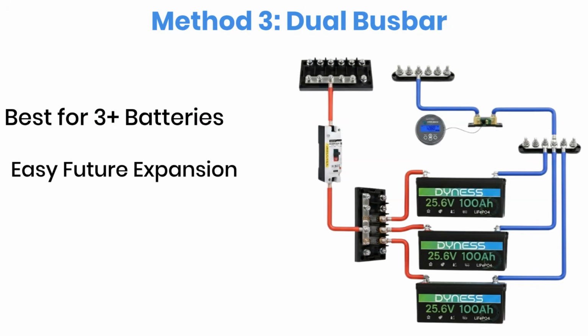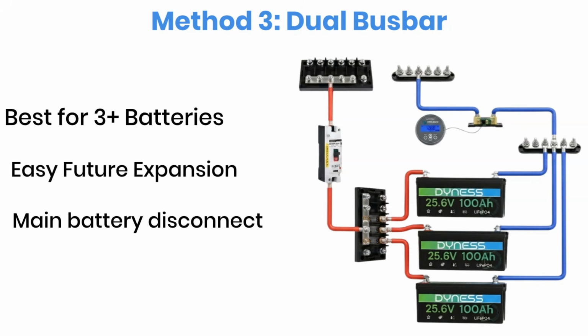Of course, because that main cable carries the combined current from all of the batteries, it must be protected with the correct overcurrent device. That could be a properly rated direct current breaker, a Class T fuse, or an NH0 fuse, depending on your system design and the fault current you're expecting. This layout follows the same basic idea used in many professional battery distribution systems. The difference is that you can often build a very similar arrangement using standard bus bars and fuse blocks for much less money. Now let's compare the cost of all 3 methods.